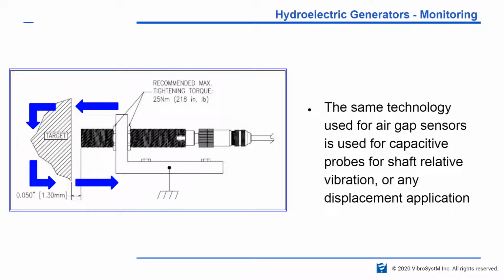And the beauty of those probes is that since we create an electrical field, the surface material is inconsequential. It doesn't really matter what type of material is present. It doesn't matter if it's copper, brass, titanium, steel, carbon steel, iron, rust. So long as it's conductive or semiconductive, the performance is the same. The electrical field that is created creates a certain amount of current depending on the distance. Without going into all the physical details, we create a capacitor, and all the parameters are controlled with the exception of the distance. So any variation in the amount of current that flows through can only be attributed to a variation in distance.